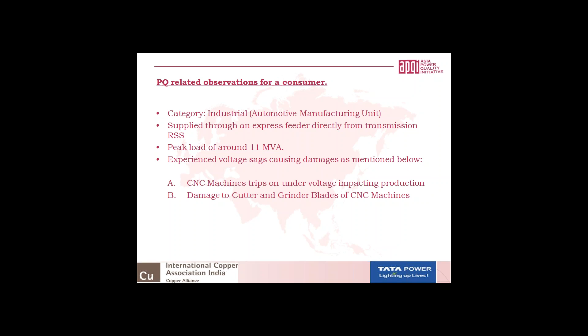The peak load of this consumer is around 11 MVA, and the customer was experiencing voltage sags. These voltage sags were resulting in tripping of the CNC machines due to under voltage, which was impacting the production, and there was damage observed to some cutter and grinder blades of the CNC machines. This was the problem reported by the consumer.